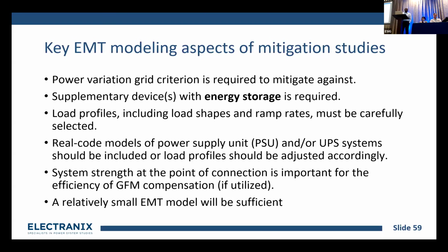So energy storage could be batteries or supercapacitors, or any form of energy storage. You need something that can store energy and then discharge into the grid or absorb, in such a way that you can flatten out that power curve where we have these fluctuations. So the load profiles, including the load shapes and ramp rates, are very important, and we have to select carefully in these mitigation studies. In other terms, you can select a load profile that passes the requirement and one that fails the requirement as well.